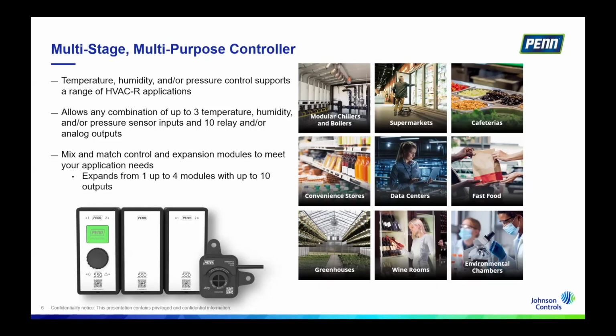Supermarkets, there's a lot of applications here ranging from display case control temperature to a combination of evaporator temperature control, defrost control, and in the commercial refrigeration space, we support all 3 defrost types. So we support off-cycle defrost, electric defrost, and hot gas bypass defrost. And a 4th one that is part of the electric defrost is what we call demand defrost, which is a smart defrost algorithm that actually optimizes the defrost cycle by determining how long it took over a period of time to actually defrost that coil.